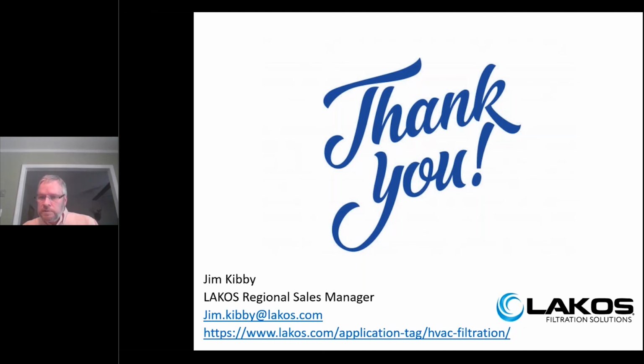I see one that says, I don't like to use water treatment hooked up to Lakos. If the Lakos fails, water treatment fails. Yeah, it's not set up for that. Some water treatment people try to do that. We try to get away from it. Sometimes they try to take over our controls and set our purge to blow down the tower. It's not designed to do that. It's designed just to purge the solids that are in the separator.